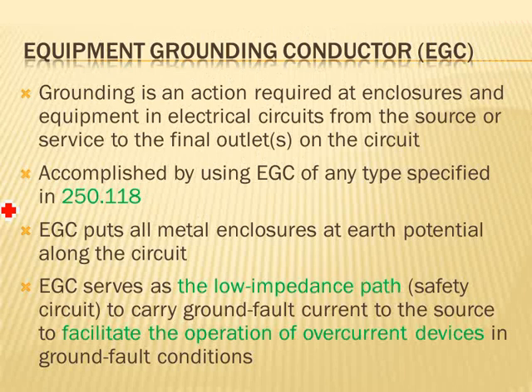So if you were to change the ballast on this and it's not grounded, and you're barefoot in a basement on a metallic ladder, so make it a perfect shock, and that frame is energized because of a malfunction in it, you grab into that frame of that light, which is metallic, current goes right through you. That's what we call the perfect shock that sends you to the Lord so fast. So someone smarter said, what if we grab a wire and tie it to the frame of that fixture, right? That wire is called the equipment grounding conductor.